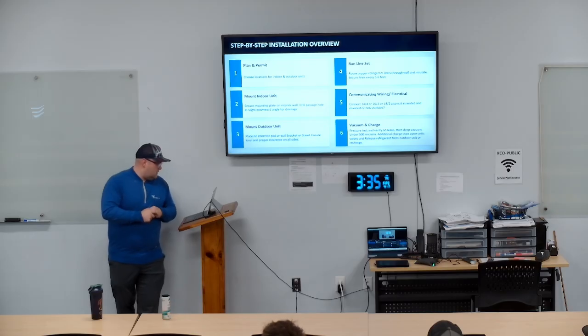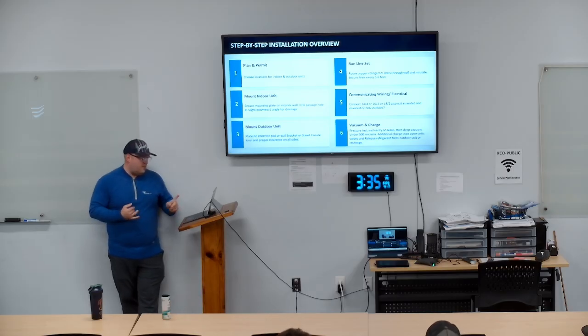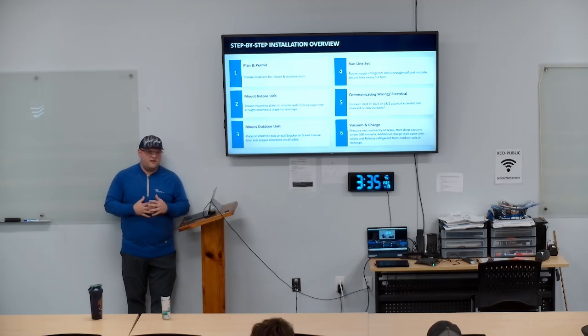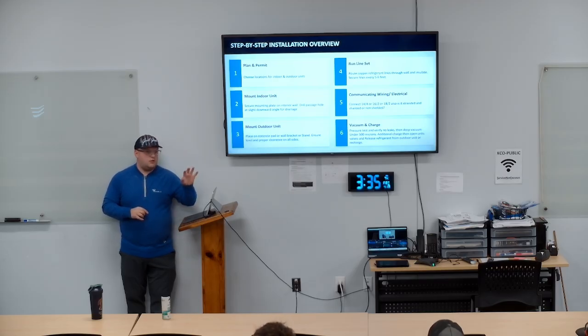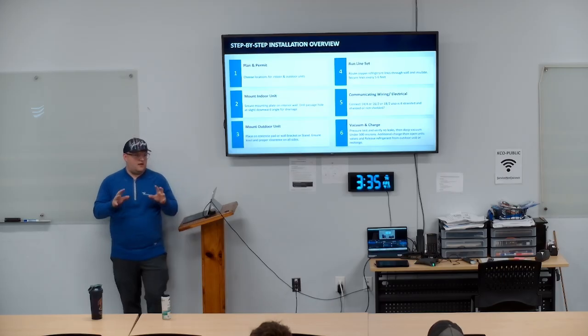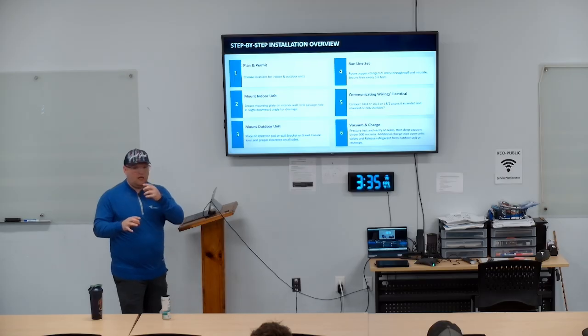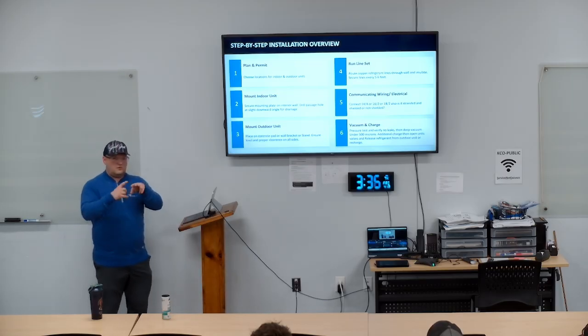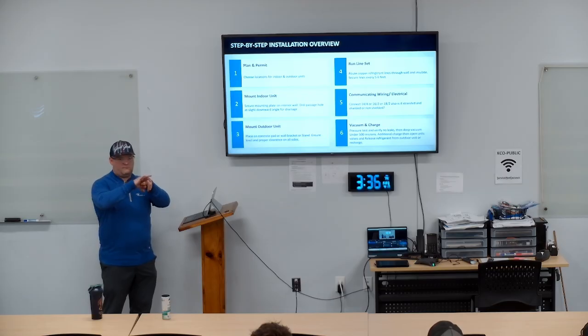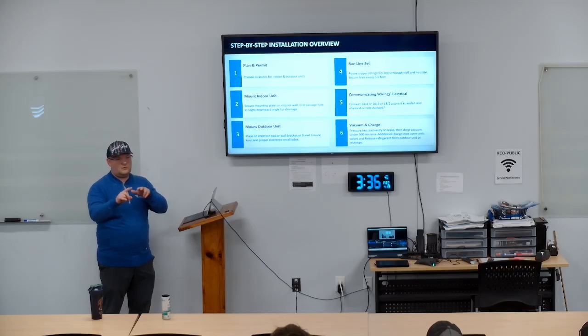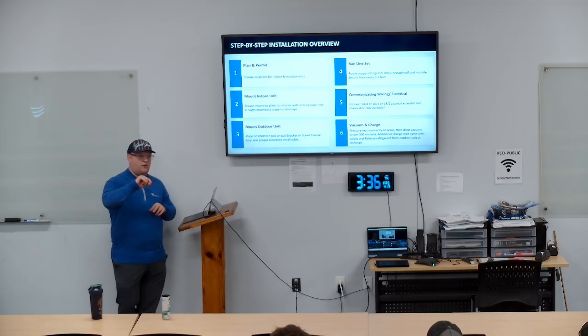So yeah. Also, the other thing to think about with that is, is it shielded or not shielded? That actually matters. I'll tell you, we've had instances where people say, just run shielded, it'll be good, right? Because everybody knows what a shield is, right? So if I have an 18-2 wire, it's going to be two conductors coming through. They're going to be sheathed single in the same piece of insulation. And then there's a bare wire that runs through it. That bare wire wraps to the ground.